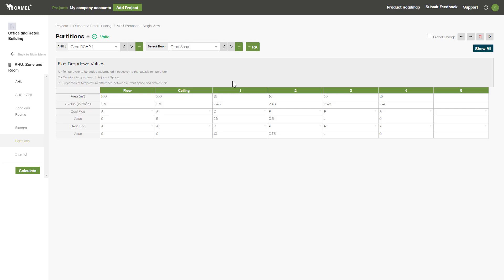Another option is to use the A flag. This sets the adjacent space temperature at the ambient air temperature plus the number entered into the value field. In this example, the space above the ceiling is at the summer ambient temperature plus 5 degrees for cooling mode, and for heating mode it will just be at the ambient winter design condition itself since zero has been entered here.